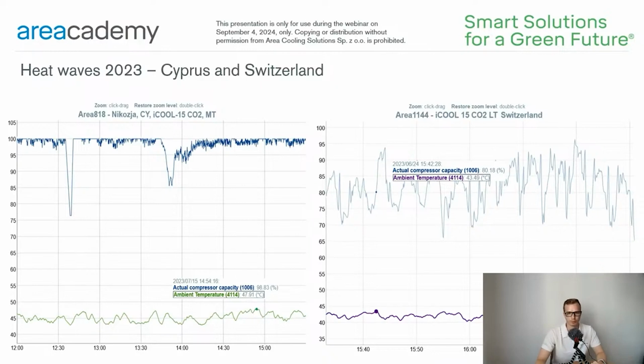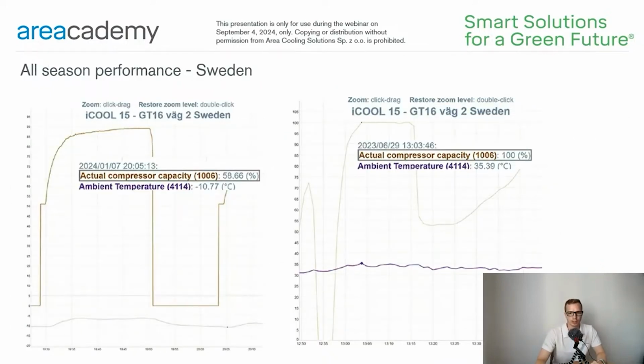This slide, in turn, shows the operating diagrams of an iCool CO2 unit installed in a store in Sweden. Both charts refer to the same unit in the same store. As you can see, our iCool CO2 units are characterized by all seasons performance. They can work well at low temperature, like we see on the left diagram, where there is almost minus 11 degrees Celsius, and also when the ambient is high, nearly 36 degrees Celsius in the graph on the right.